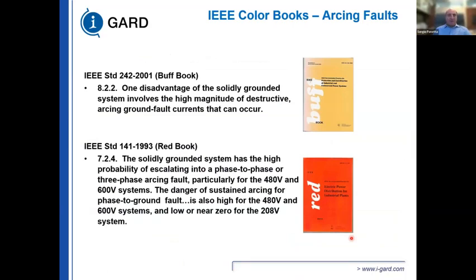Going back to the Buff book, one disadvantage of solid ground system involves the high magnitude of destructive arcing ground fault current. You have to keep in mind that when you have a ground fault in an electrical system, that ground fault current has to return back to the source. There is no impedance in that ground fault. The only impedance you have is the impedance of the transformer and the impedance of the ground fault itself. So you're going to have a great magnitude of current flowing in that ground fault. And this is what was meant by high destructive current.